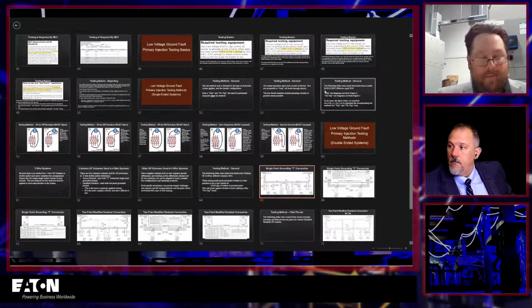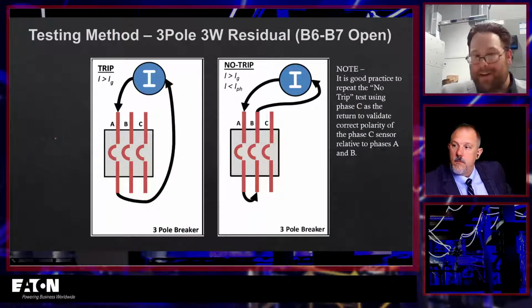Yeah, and I'll go back to a point I think I made last time I was here with you. When I first came into this industry and got hired with Eaton, I was going through what does Eaton do? Huge manufacturer of equipment. I'm imagining our Arden plant, our Sumter plant, Asheville, all the places we manufacture this equipment, and I'm picturing Ford-like processes where you have these product lines, and the switchgear just moves down this rolling conveyor and parts are put on, because a switchgear is a switchgear. A switchboard is a switchboard. But that's really not how it is. If you go to our factories and walk the floor, you find out there are no conveyor belts, no moving lines of equipment, because every piece of equipment that's manufactured is custom. Every switchgear looks a little different, has a little different functionality, and those details are important in what we're discussing here.